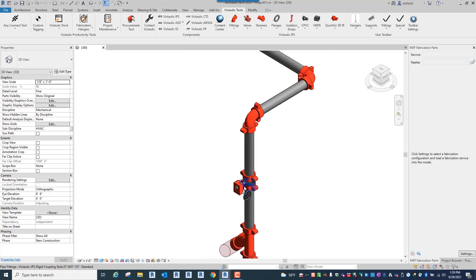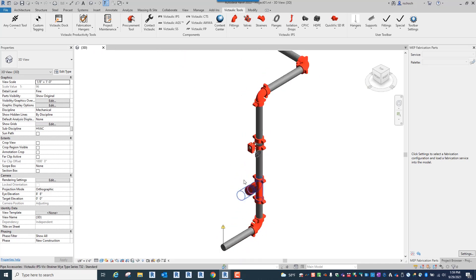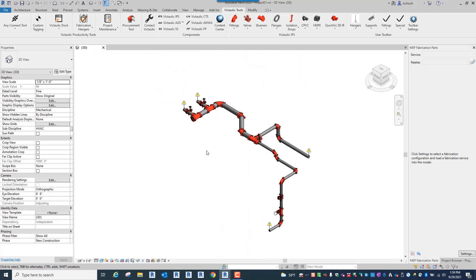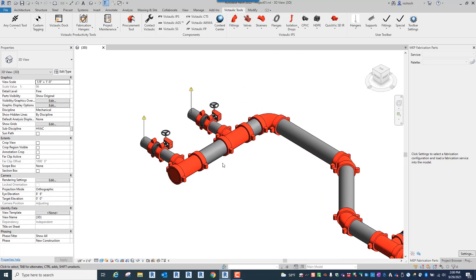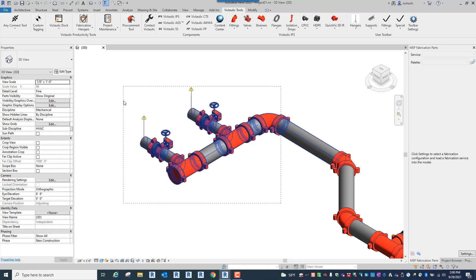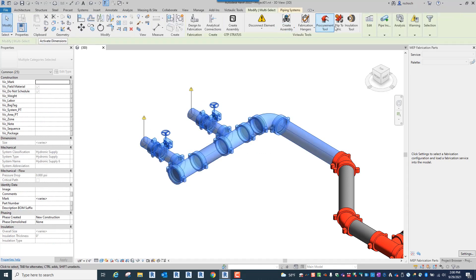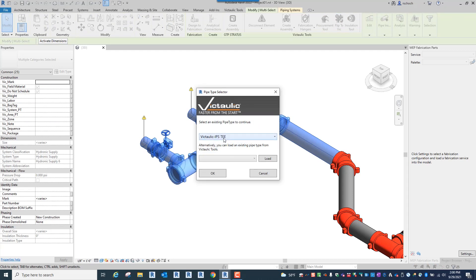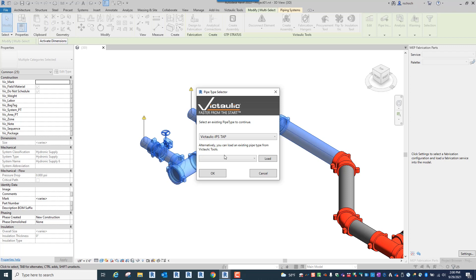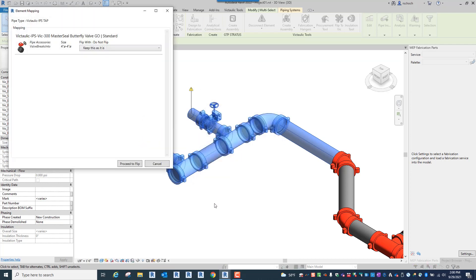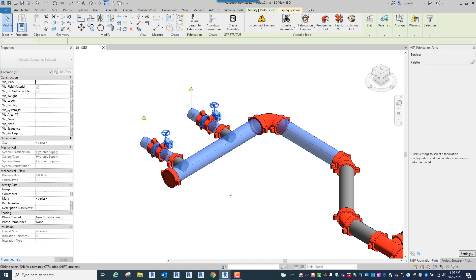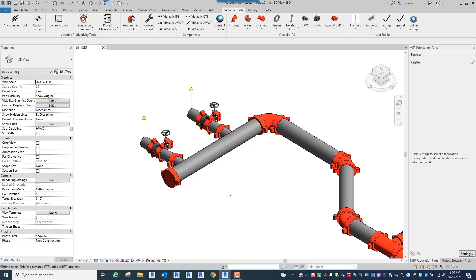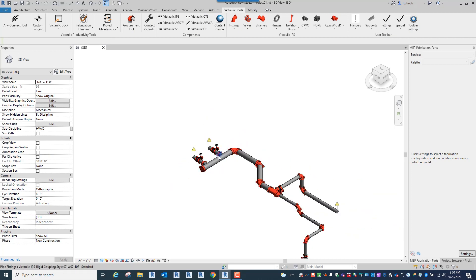You can see here's the valve that was converted. Here's the strainer. Now a lot of times we have scenarios where maybe we don't want to use tees like this scenario here. We have a component, it's our number 26 outlet fitting. I can take this model, this area of the project just window select. I can actually use Flip2Vic to just change out from tees to taps that quickly. So if I want to put in our number 26 outlet fitting I can just select that tap pipe type. I can say leave the valve as is because it's already Victaulic. We're good to go. In a few seconds there you go. It changed it out to our number 26 outlet fitting. So what you could do there is you could detail that out and send it to us and we can provide you that part.